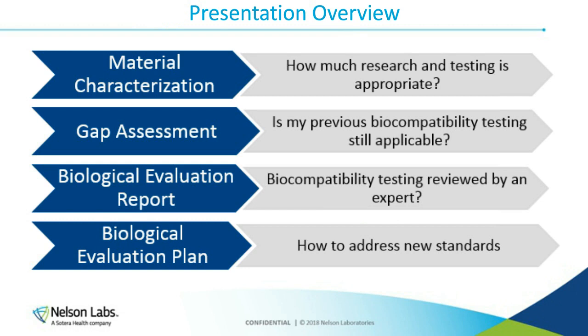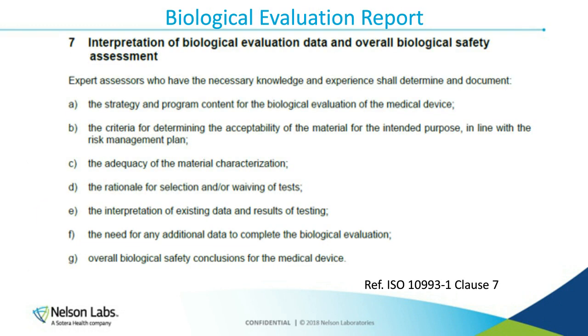Okay, so now we're going to move on to a biological evaluation. The big question here is, was the testing reviewed by an expert? This comes specifically from Clause 7 in ISO 10993 Part 1, where they outline what's required when you review these reports and how you should understand it from a bigger picture perspective as well. This is really wordy. I just wanted to put this here so you can go to your 10993 standard, review that, and make sure your biocompatibility program includes this final portion.